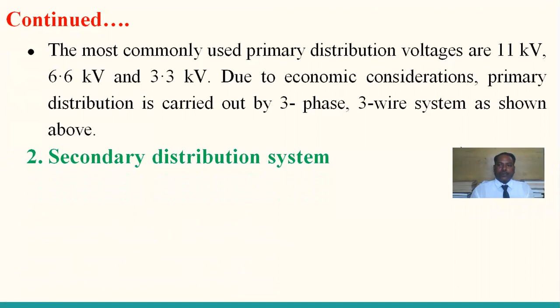Similarly, the secondary distribution system. What is the secondary distribution system? The primary distribution system commences from the distribution substation onwards up to the distribution transformer primary. But the secondary distribution system commences from the distribution transformer secondary onwards up to the consumer port. It is part of the AC distribution system. The secondary distribution implies a 415 by 230 volts, 3-phase 4-wire system.